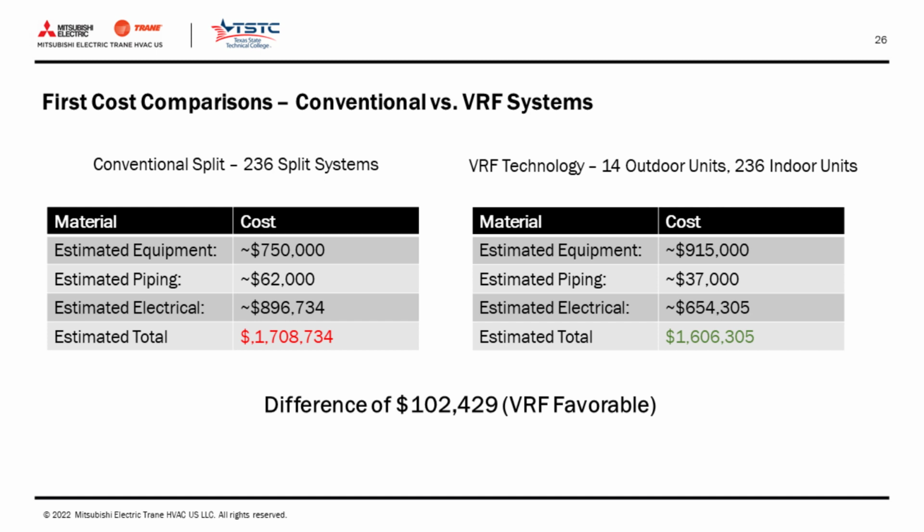This is HVAC based on individual, conventional, centralized systems that split the air conditioner and heating equipment. These solutions get installed all the time, but not only are these super inefficient, they are a cost and design nightmare if you really consider a holistic view. Considering the piping number, each of the 236 conventional units requires a home run of refrigerant piping from the apartment to the roof. That is a lot of piping. And think of the vertical chases through the building required to fit all that piping and insulation.